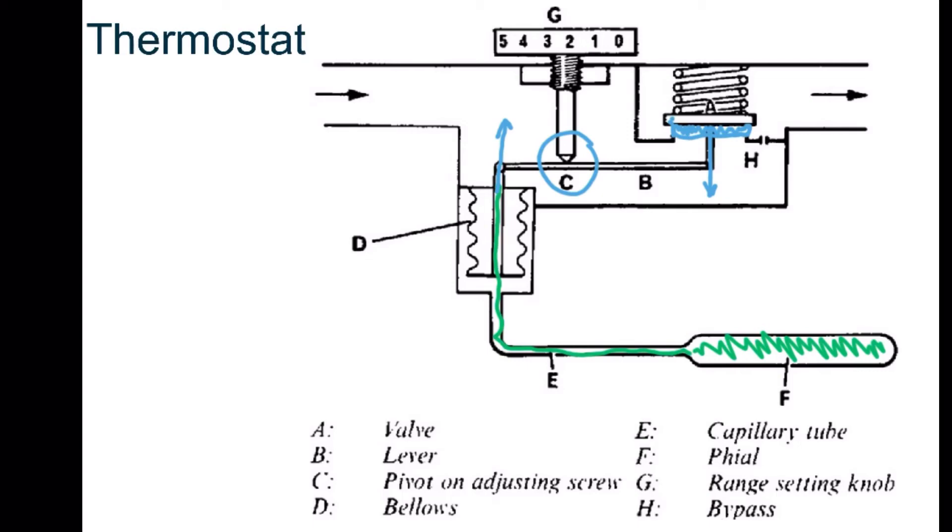Now if we left it like that, the gas would be stuck. It would come in here and wouldn't be able to get any further because the gas valve is closed. So within a thermostat, we have a small bypass hole which allows some gas to escape through and go to the burner.